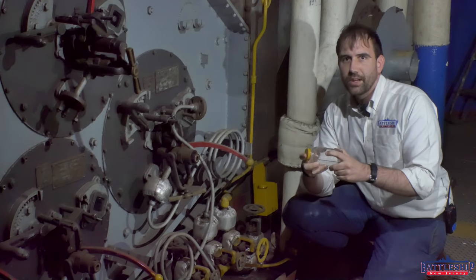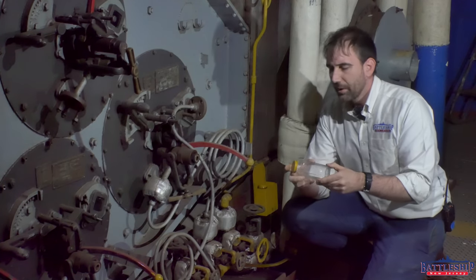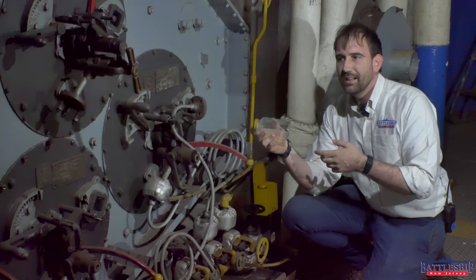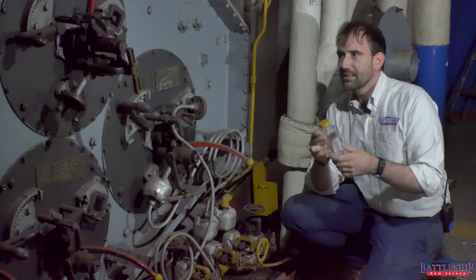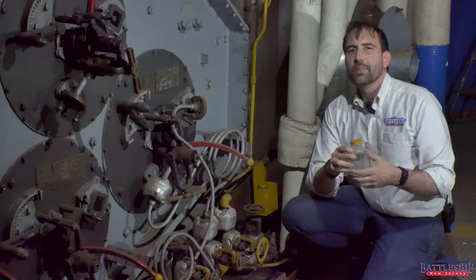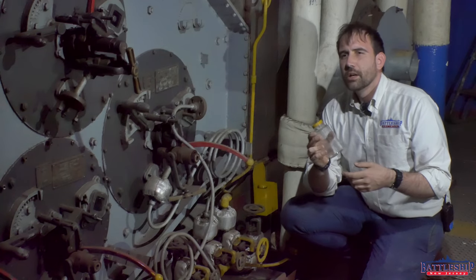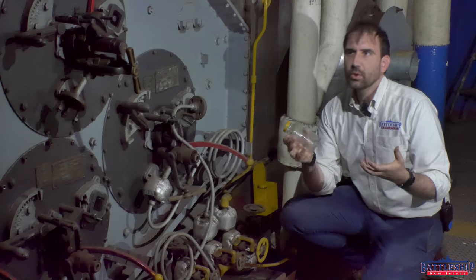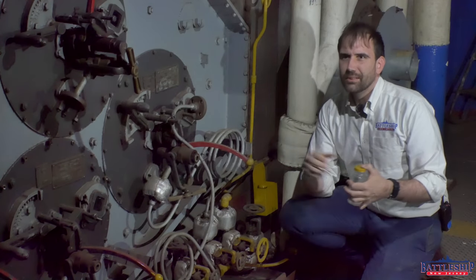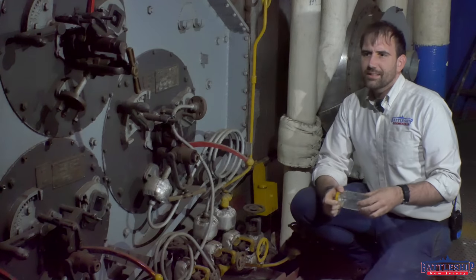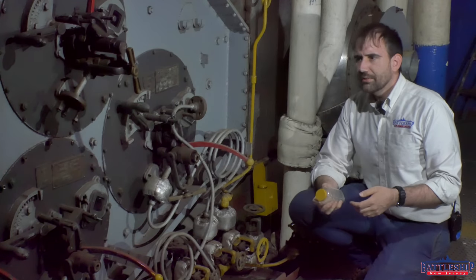DFM is diesel fuel marine, or diesel number 4, which is the type of fuel the ship was converted to burn in the 1980s. So this is how you would test the fuel oil that you're putting into the burners. That's something they would have tested every single watch back when we were burning Bunker C, or essentially unrefined crude oil. Barely refined is probably a more correct way of saying that. So that stuff they would be checking pretty frequently.